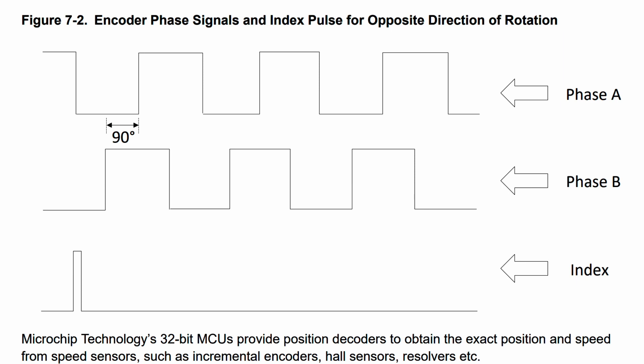If pulse A is leading pulse B — which are already 90 degrees apart from each other, so they are in quadrature — you can say that the motor is spinning in one direction. But if pulse B is leading pulse A, that means the motor is rotating in the other direction. If you want to detect speed, the number of pulse trains received in a given interval of time will give you an indication of the RPM or speed of the motor.